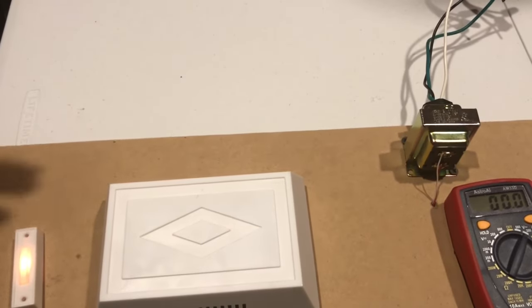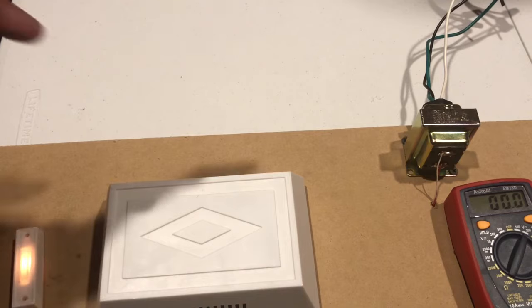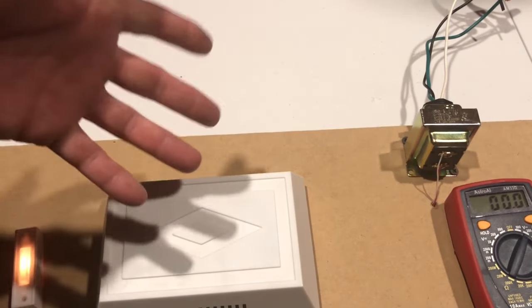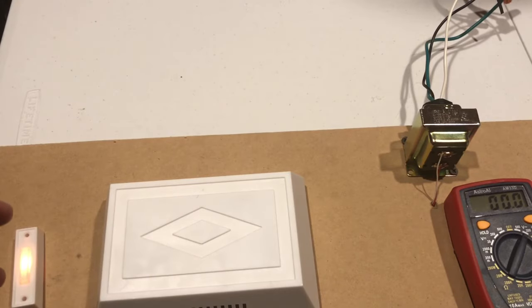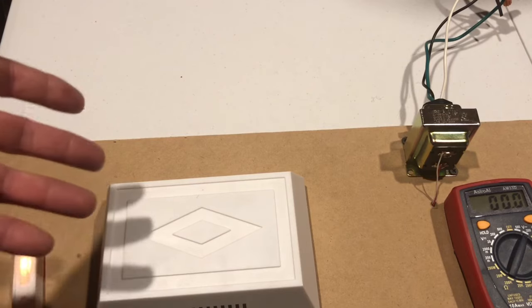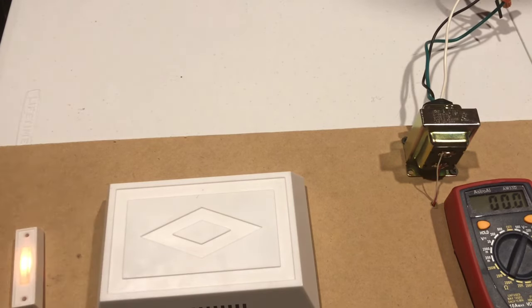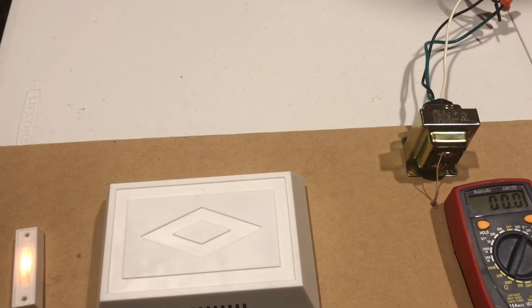So if there isn't, then we know that we got to look at a circuit breaker, or we've got to look at another outlet that may not be working. It could be that this is tied into a GFI and that's tripped, or it's just the breaker is either bad or it could be tripped. There could be a lot of different reasons.